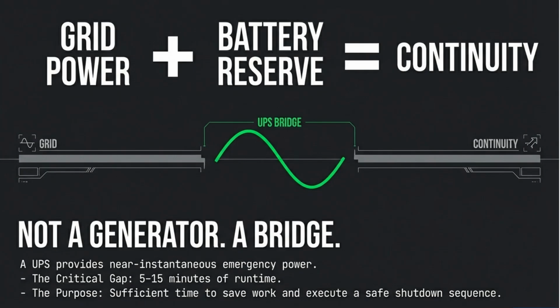A UPS is not a generator, it is a bridge. It combines grid power with battery reserve to ensure continuity, providing a critical gap of 5 to 15 minutes, allowing sufficient time for a safe system shutdown.